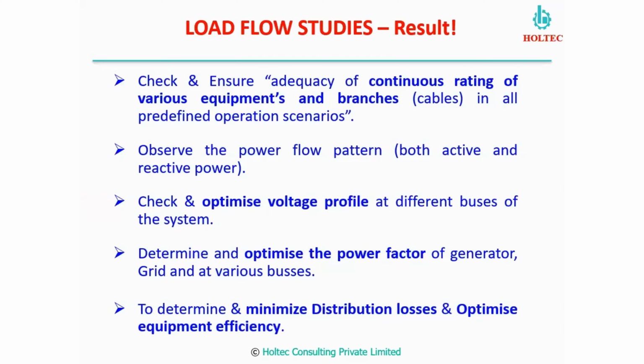Then we have to maintain not only the power sources where we have to maintain the power factor, we have to optimize the power factor on all buses. The buses means the branches from where the incoming power is coming and it is distributing to different load or different buses. So these buses power factor, all buses, whether it is MV, whether it is LV, we have to maintain the power factor. Why? Because when we maintain the power factor of that particular bus to near unity, then the incoming power which is being received by this bus from various sources, the current will be reduced. So the branch losses, the cable losses, which is a connection between the source and the bus, will be reduced. So your losses will be improved.